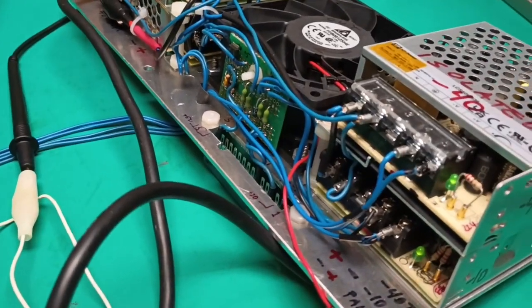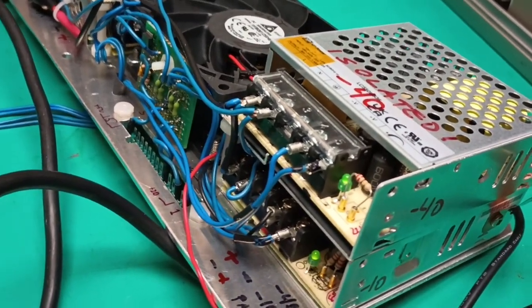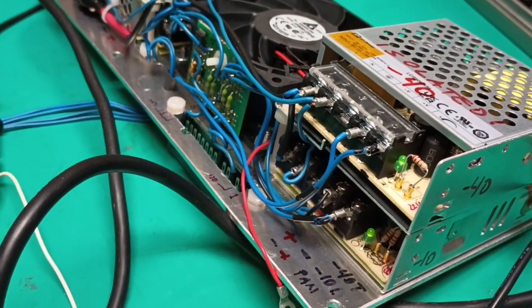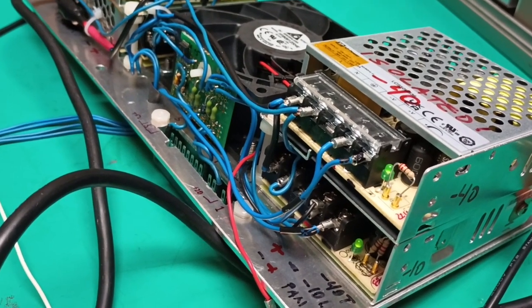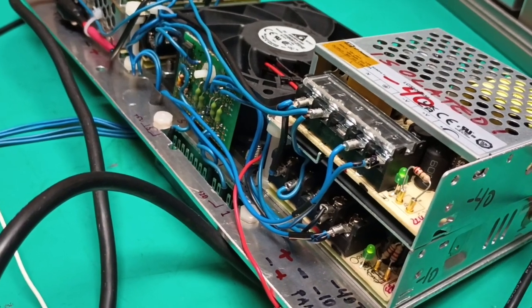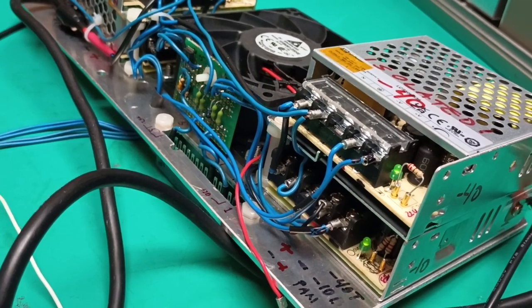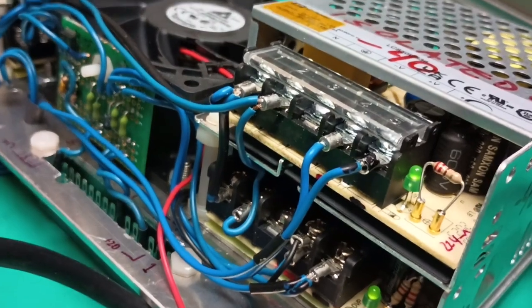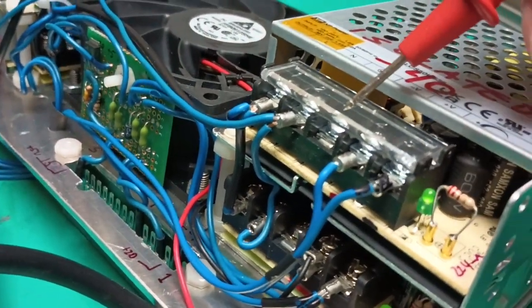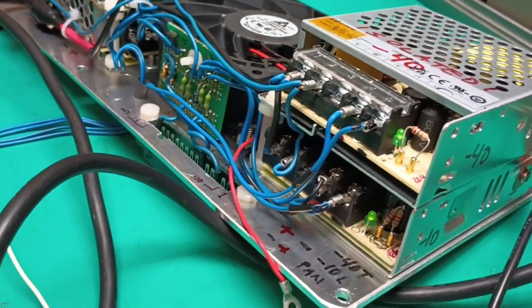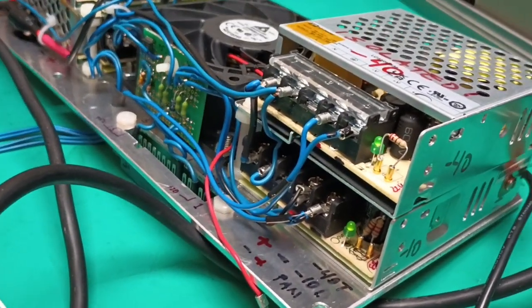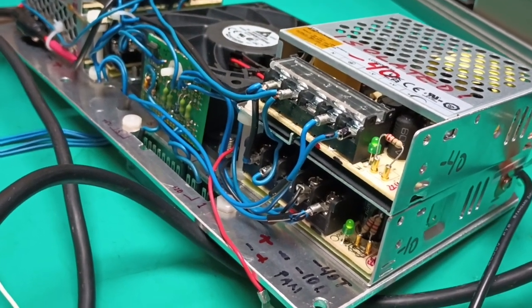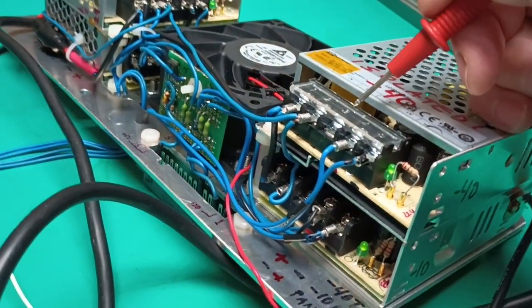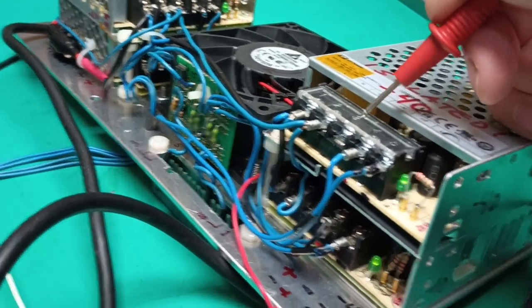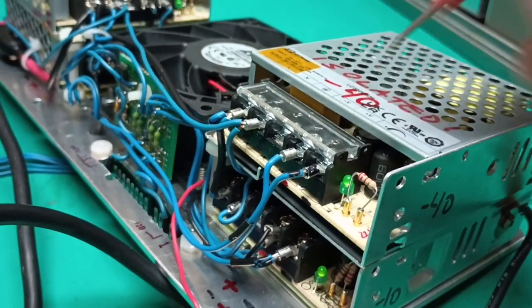And the problem that has occurred, that I was able to prove from taking these little switch mode power supplies apart, is that inside they have put disc ceramic safety capacitors from the AC line driven rectified filtered DC input to the switching supply over to that so-called ground terminal, the one here that's not connected. So since that's not connected, that's allowing the leakage current from the AC power supply and some leakage across maybe the switch mode transformer. And there's also a small disc ceramic from this so-called earth terminal to the minus terminal on the power supply unit.